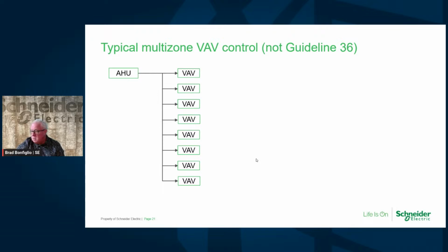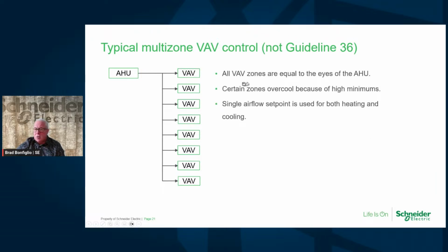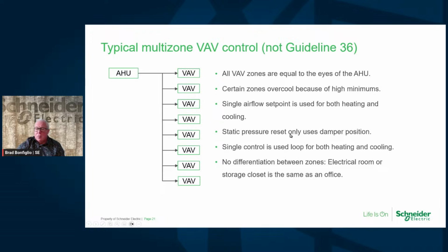So we talked about zones a little bit. We talked about trim and respond. This is typically what happens. This is not Guideline 36. This is typically what happens when you've got a typical application that doesn't involve this. They consider all the zones to be equal, okay? All the zones are overcooled because of the high mins, is typically what happens. That goes back to the reheat. And then a single airflow set point is used for both heating and cooling. That's pretty normal with how you set up a VAV air handler system. Static pressure reset only uses the damper position. There's a single control loop for both heating and cooling, only one, with a dead band between them. There's no differentiation between electrical rooms, storage closets, and so forth. So this is the traditional way you would control an air handling unit.